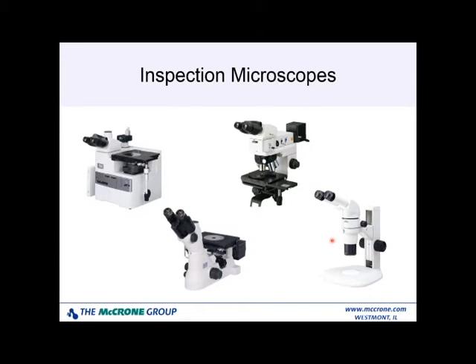This is what's called a stereo microscope. It is a rather lower power microscope. It has stereoscopic viewing to give you that 3D inspection aspect. And this particular microscope, as it's configured here on this sheet, does not have a place that you can mount a camera, but many of them do. So all four of these instruments are considered inspection microscopes. They are tools to allow you to determine surface details, features of the part, but are not measuring instruments.